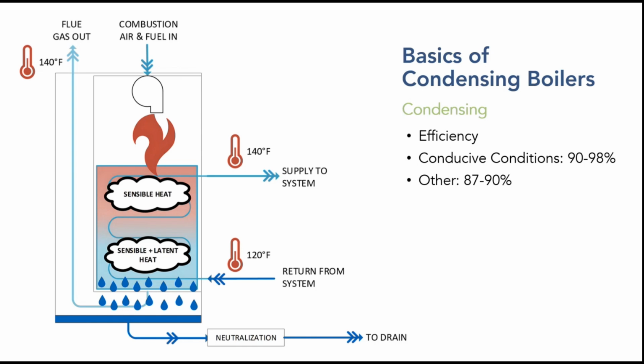That condition is purposely avoided in conventional boilers because they are not made out of materials that can withstand the acids that drop out of the flue gas. The difference here is that with more advanced materials on your heat exchange coils, they are resistant to those acids, and you can condense in your flue gas, and it's not going to corrode the boiler. That is an active process. When this is in condensing mode, you are consistently dropping water out of the flue gas, so that water is being drained out, and it has to be neutralized before it's sent to drain.